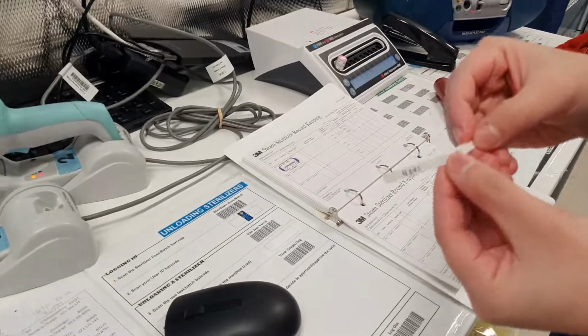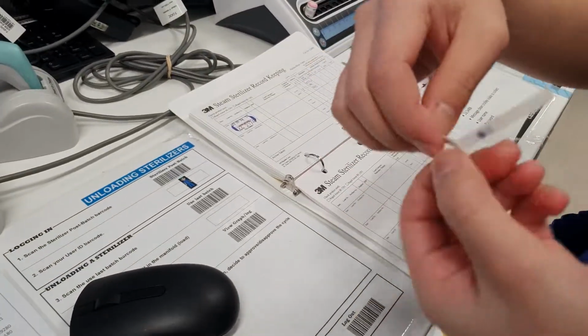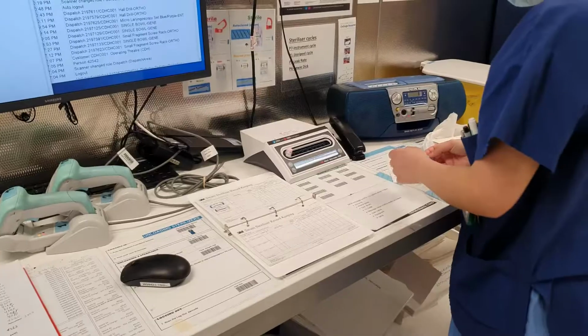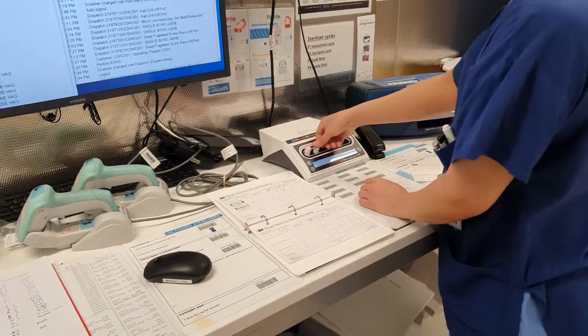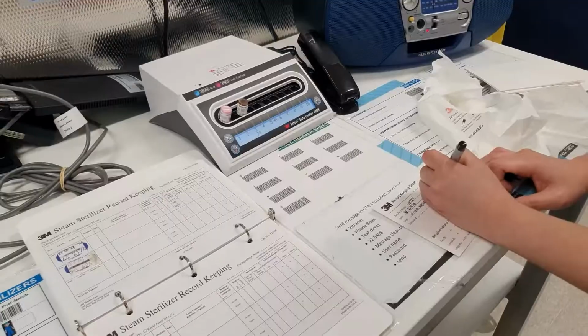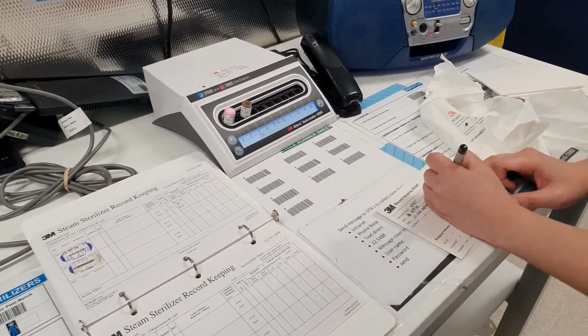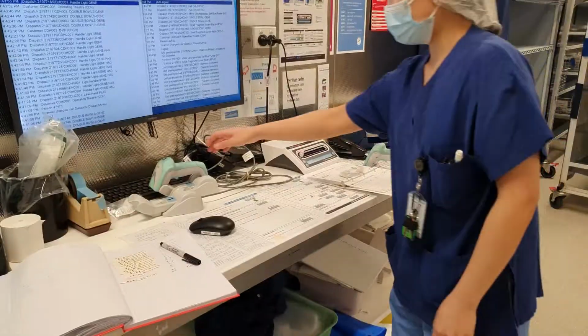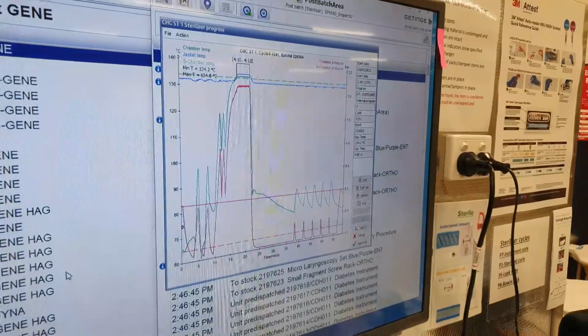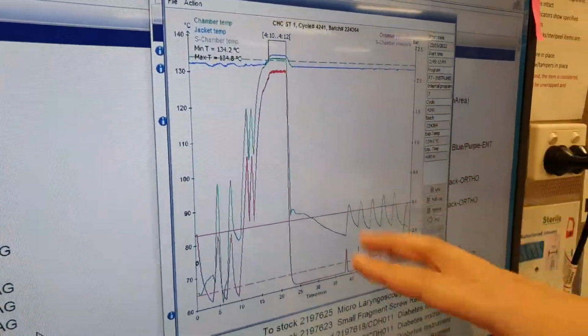Chemical indicators must be recorded, whether the cycle has passed or not. Same goes for the spore tests. If any of these tests fails, then all items from the last negative test must be recalled. We then scan the load to approve the batch and check if correct parameters are met.